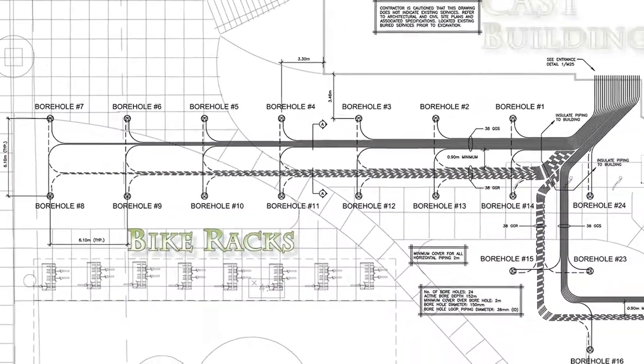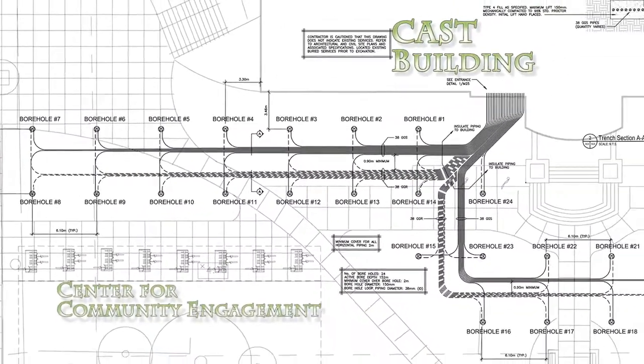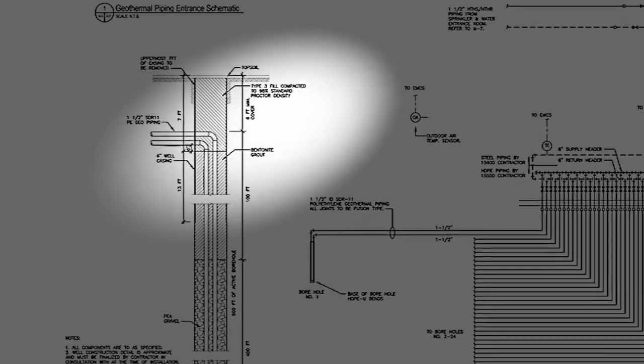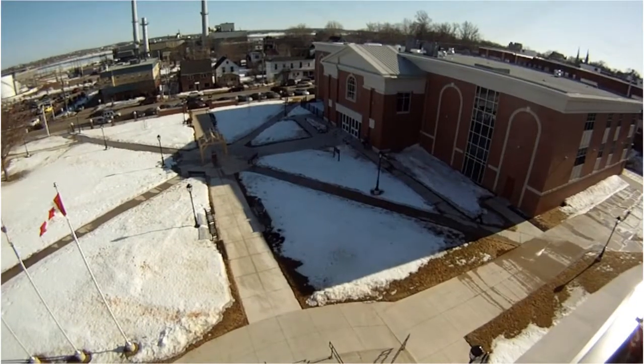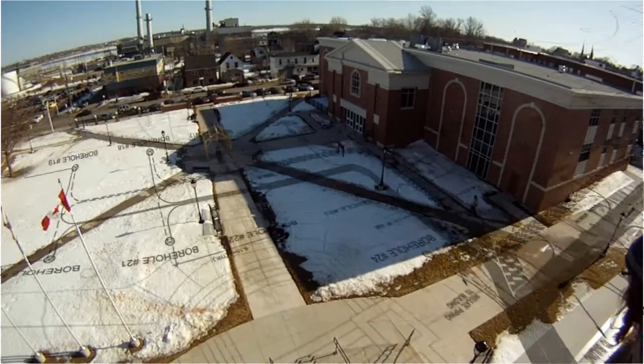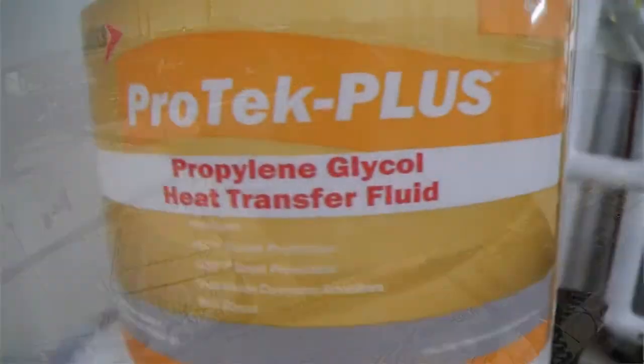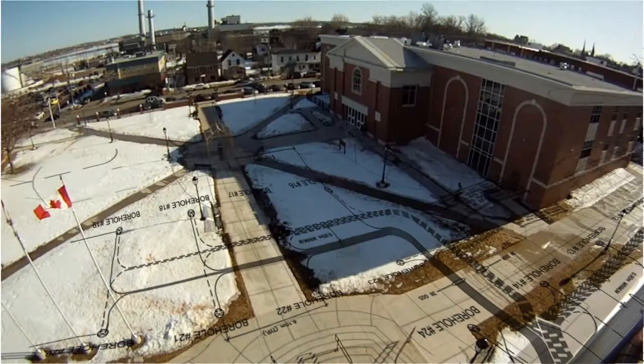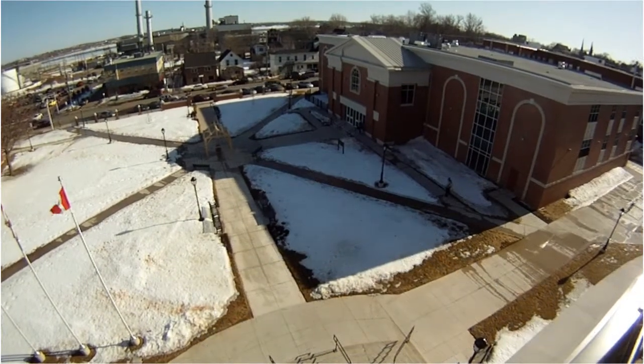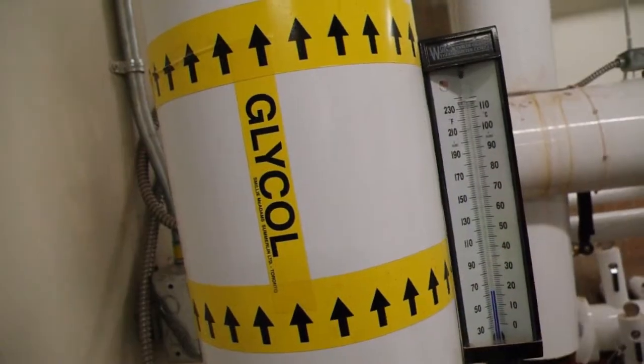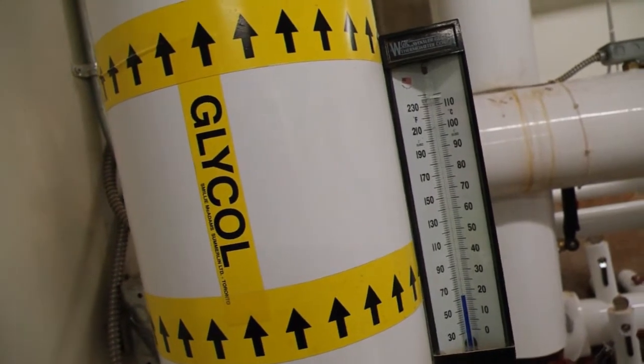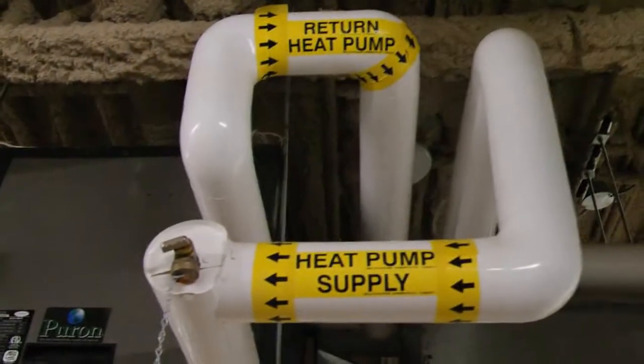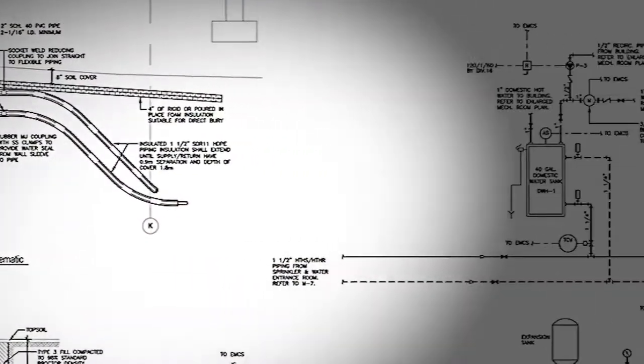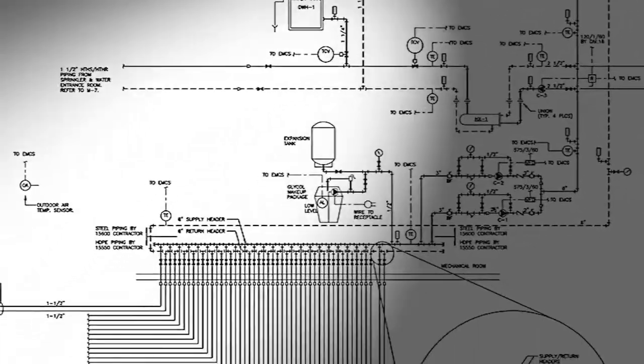Buried beneath the courtyard and under the bike racks are 24 boreholes. Each borehole descends to a depth of 500 feet below grade. Here you can see how the boreholes are laid out with a 50-50 mix of propylene glycol and water. In heating mode, when the air temperature in the building is cooler than the underground temperature, the water glycol mix transfers heat into the building through heat pumps. In cooling mode, the opposite occurs as the building's air is warmer than the underground temperature.